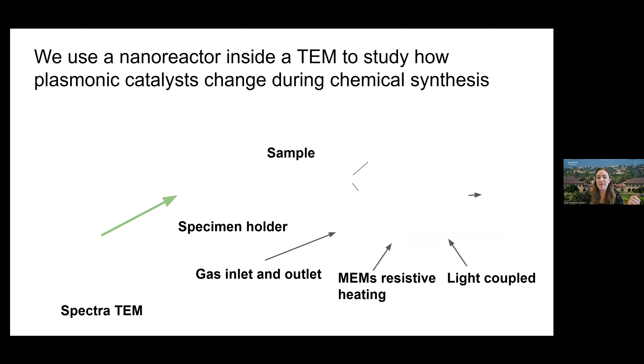Enter TEM. We use a nanoreactor inside of a TEM through a custom-built holder that allows us to flow gas mixtures in and out with different flow rates at near atmospheric pressures. We can actually go slightly above atmosphere. We can reach temperatures upwards of 1,000 degrees Celsius, and using fiber optic cable, we can couple in light and shine light on our sample, so pretty much do photocatalysis in the TEM.